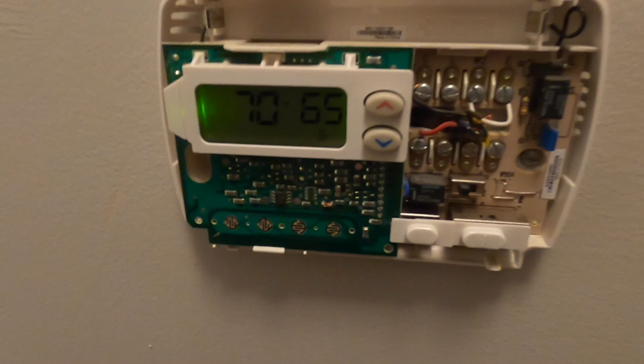Now the easiest way to double check all this, again, it's easy to access these at my thermostat, so I'm going to check it there. Again, you got your R terminal and your C terminal. That's your voltage coming in, just to verify that your multimeter works. If you don't get voltage from your R to your C, then something's wrong. But anyway, keeping the one probe on the common terminal, I know that I should have voltage on the fan. Yep, the fan was running.